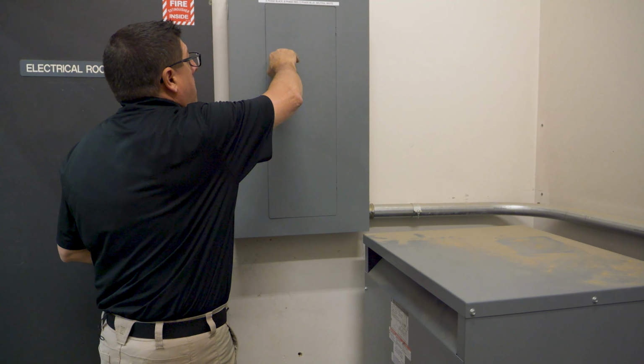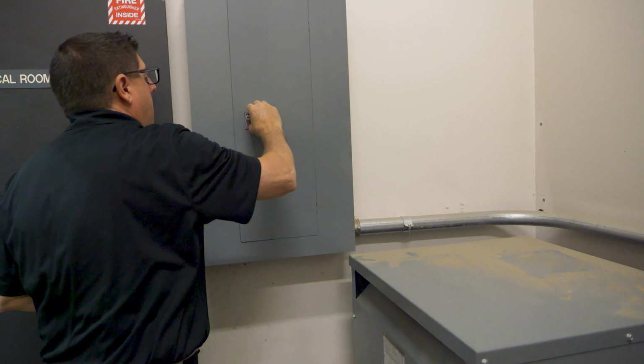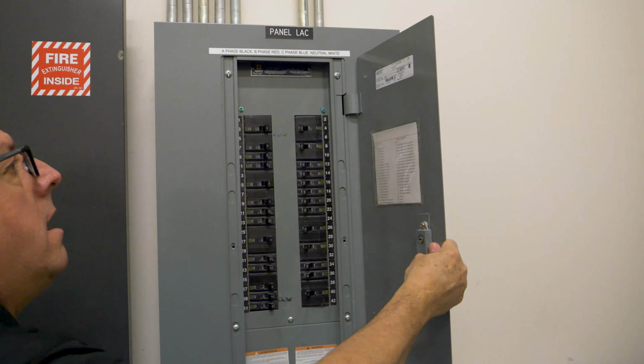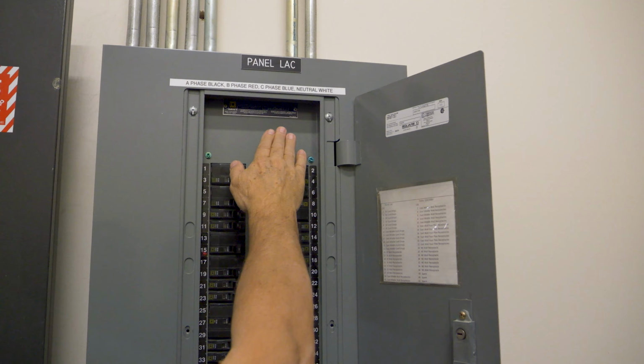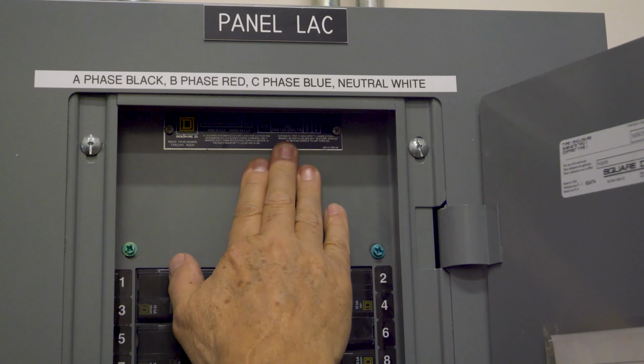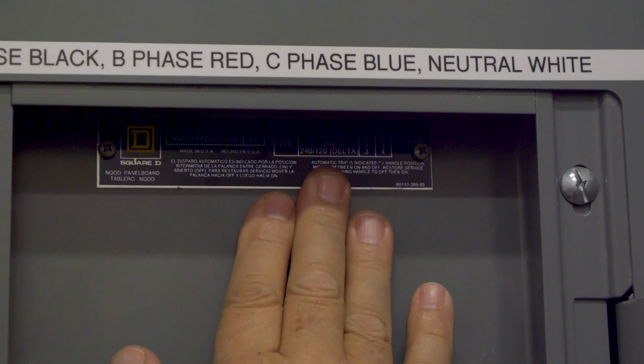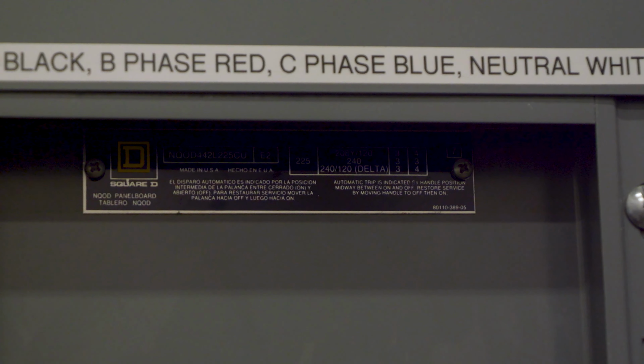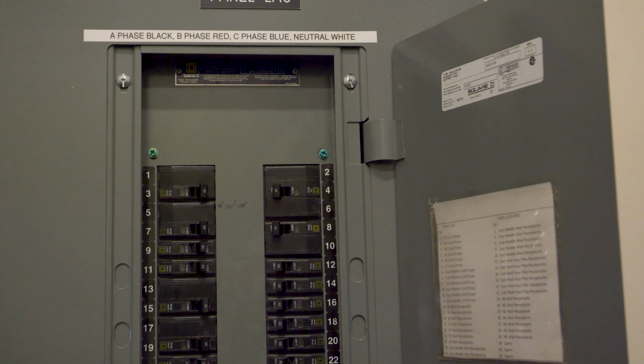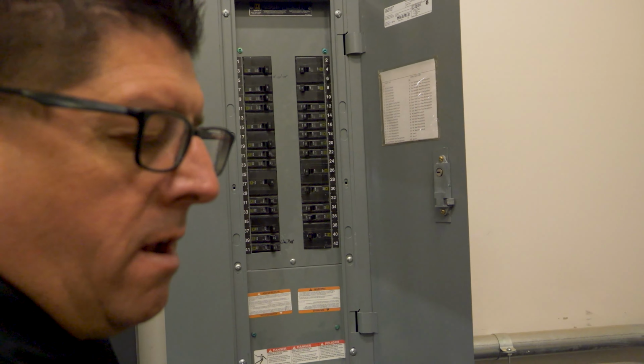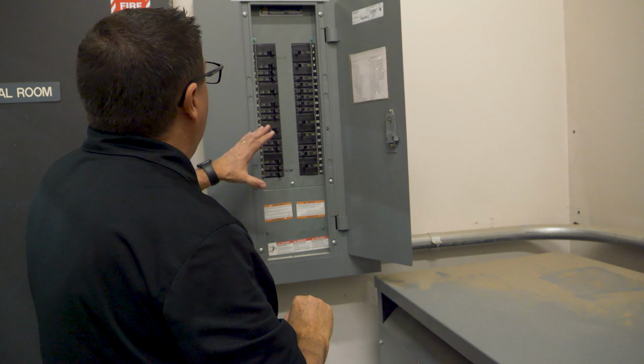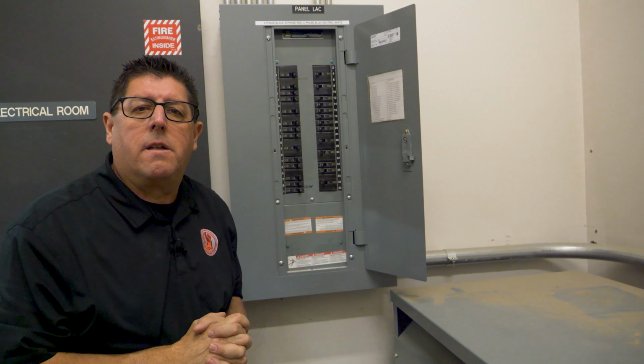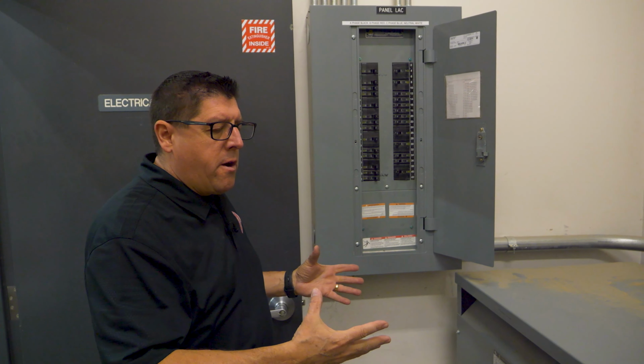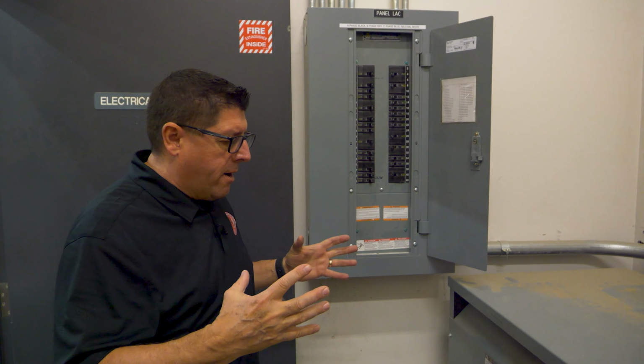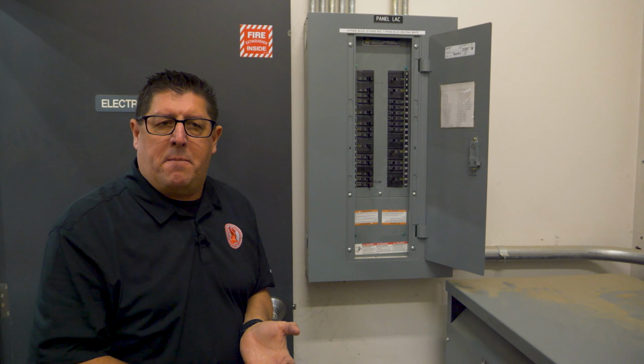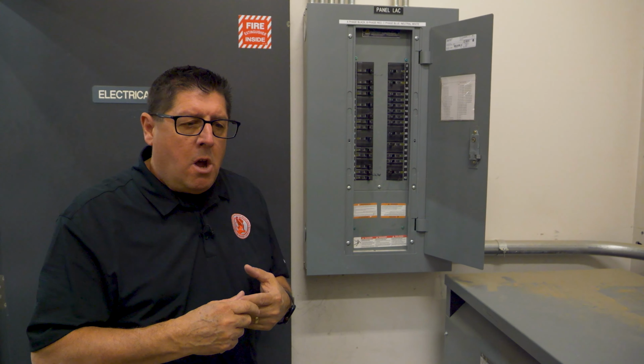And this panel is labeled lighting panel, and it is rated at 208/120. Its main disconnect will be located in the disconnect that we have next to the transformer, and it is servicing that panel.